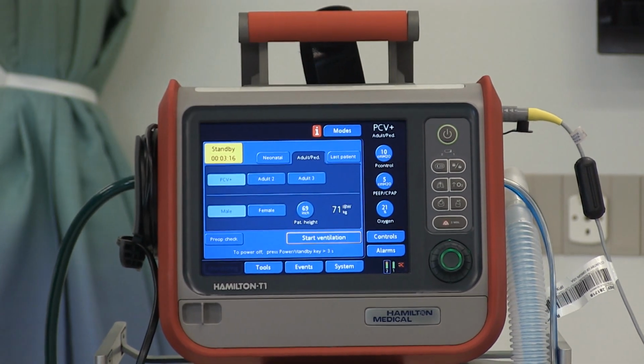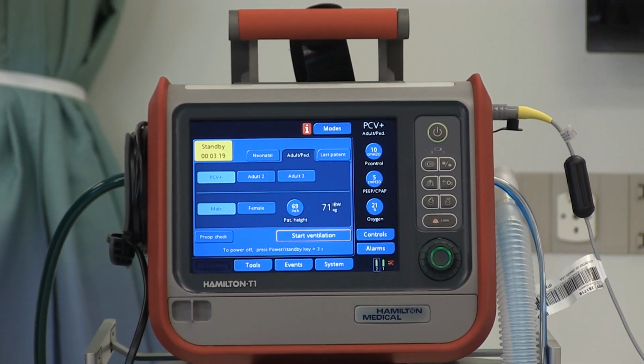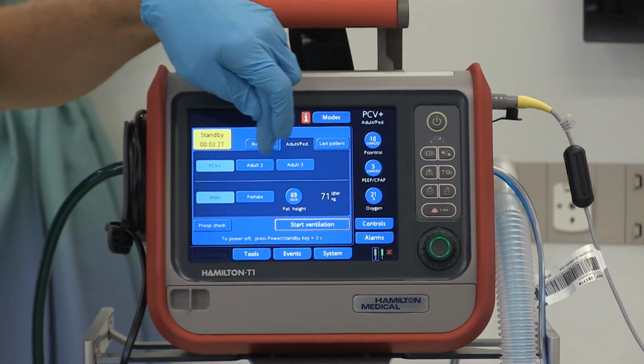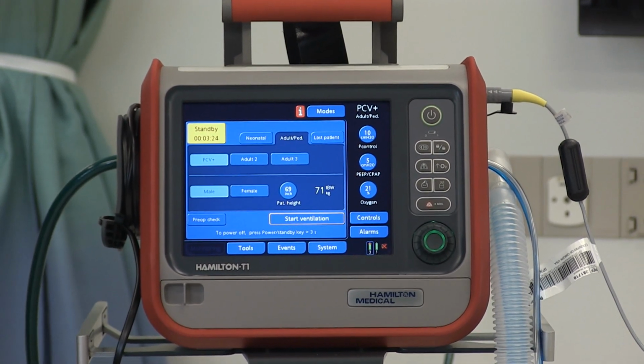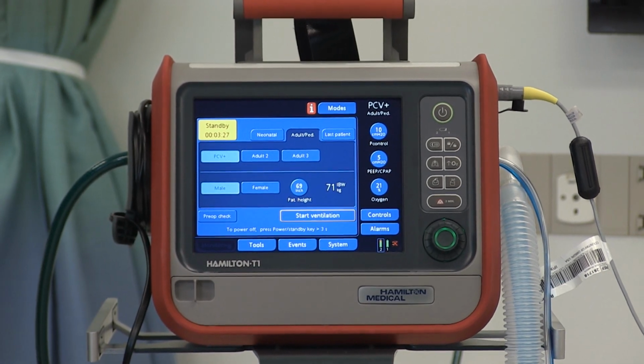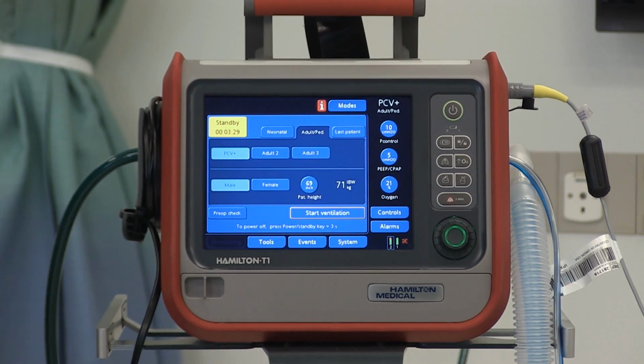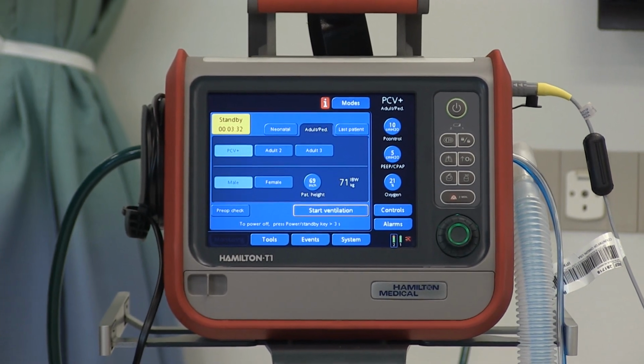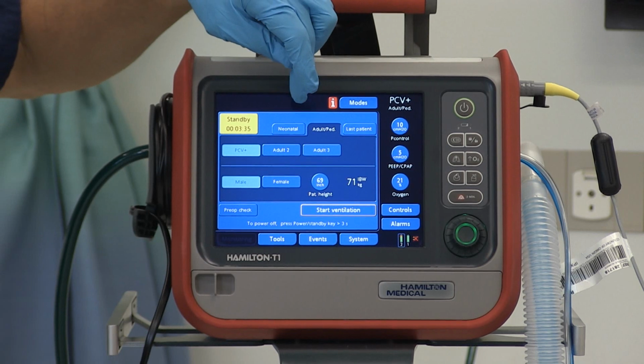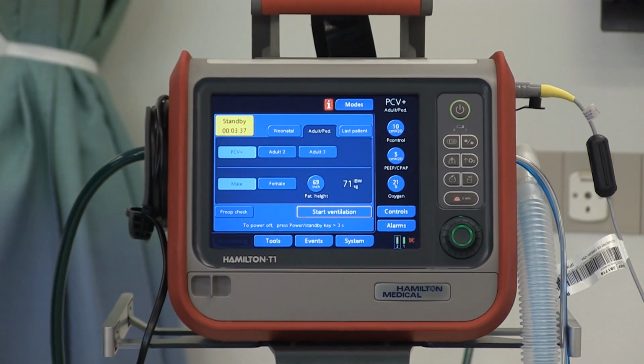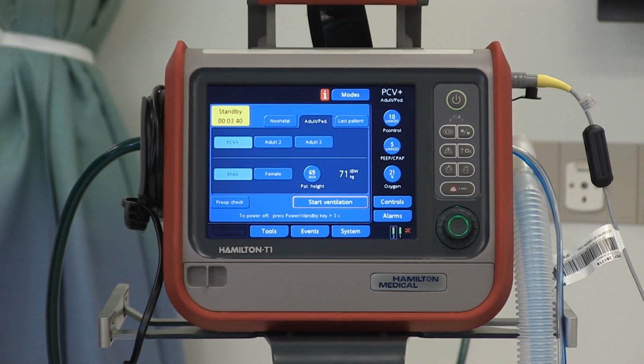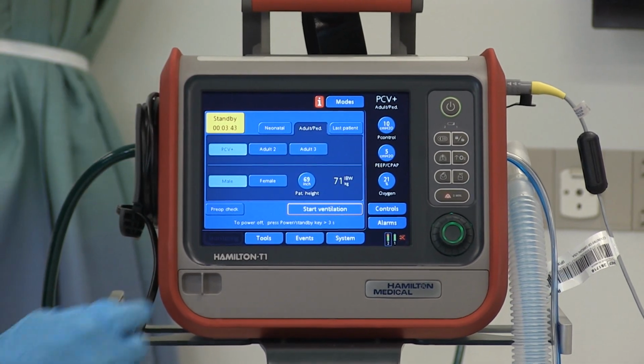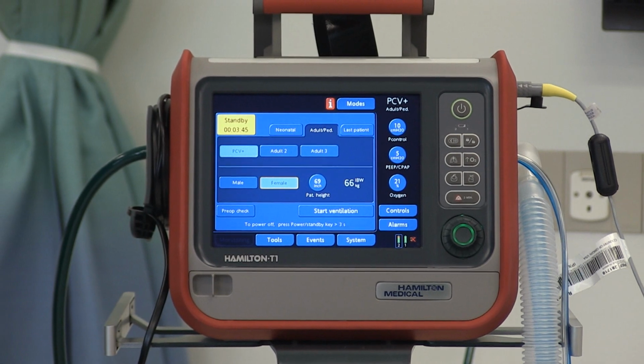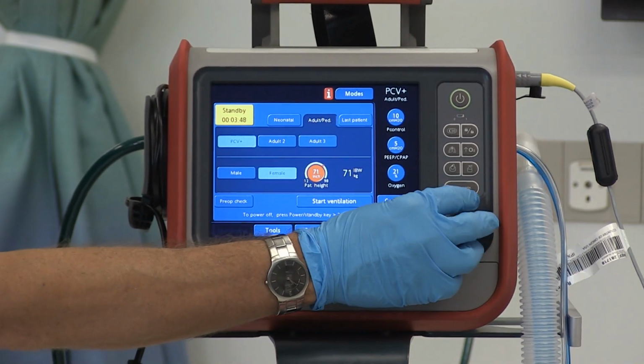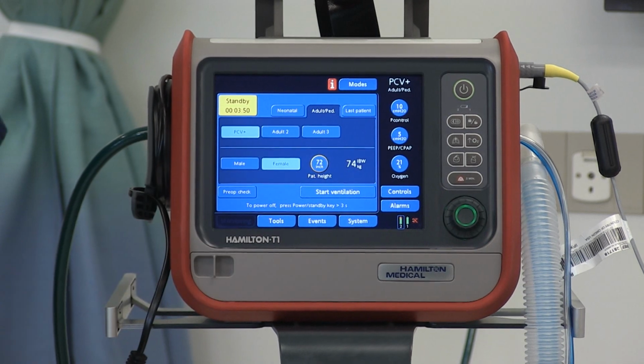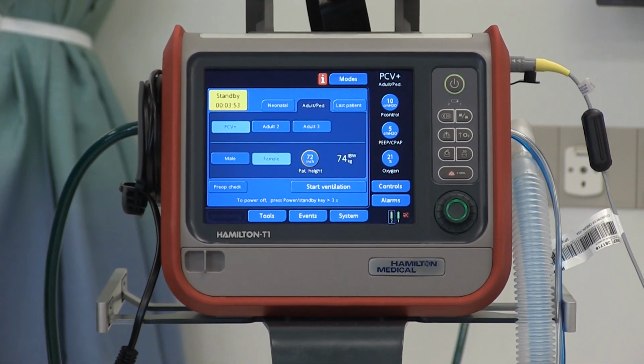Okay, and going back to the adult pediatric, this is the screen you'll see when the ventilator starts up. There's 3 quick start tabs here. Those can be set up as custom modes for emergency situations, such as if you just want to go into pressure control very quickly and not have to go through all the settings right here. And then below that is the selection for patient gender and height. So in this case, we're going to select a female patient, and we're going to adjust the height to 72 inches. And you can see the ventilator has calculated the ideal body weight for you.